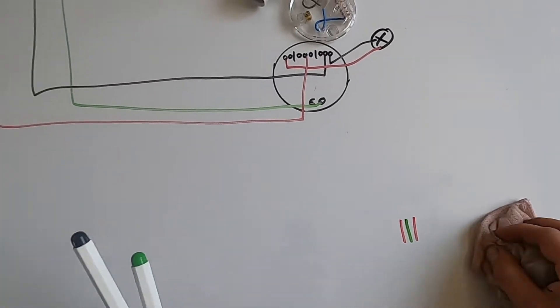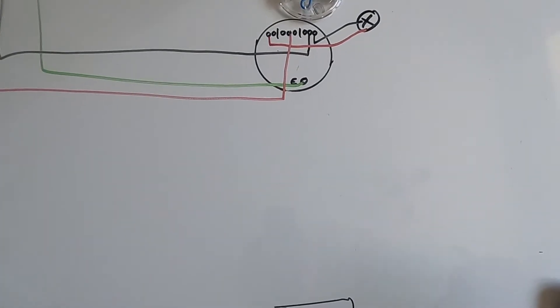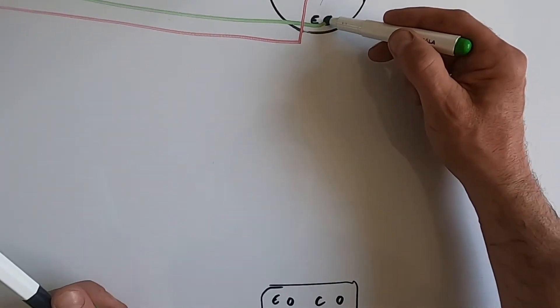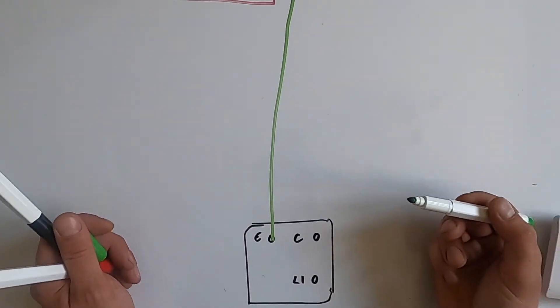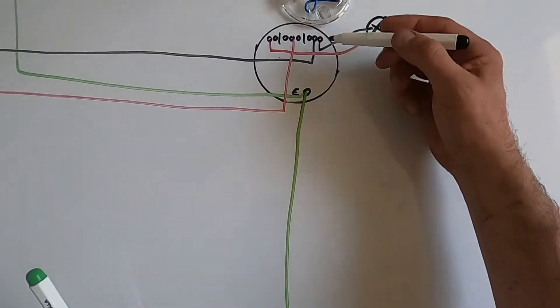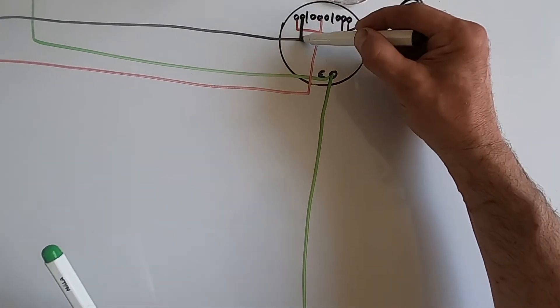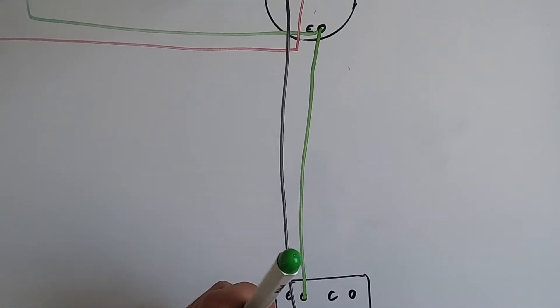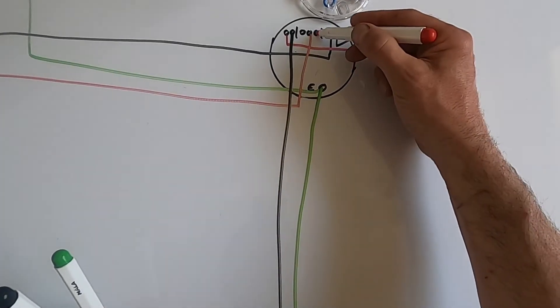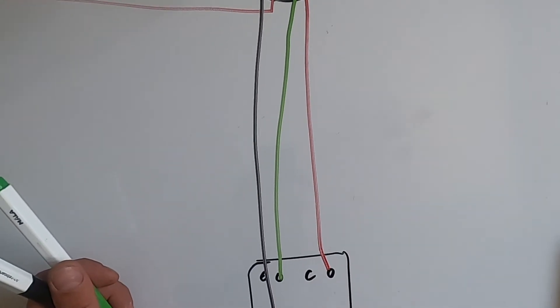But nine times out of ten, people have just used the same cable that they've used to wire the board, so we'll just use the same in this drawing. So we're going to use the earth out of the ceiling rose, that'll come down to the switch. And then the neutral in that cable, we're going to take to the live. And then the neutral - and then the live, sorry, out of that cable will take straight to the common. But then because this is going to be classed as a live, we're going to need sleeving on this live cable.